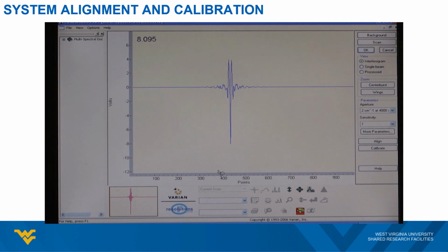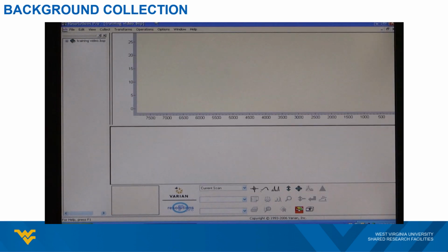With both alignment and calibration completed, click on the OK button on the right, and this will bring you back to the scan window. Now we are ready to perform the measurement. In contrast to other spectrometers, such as UV-Vis, an FTIR measurement typically involves 2 steps: capturing a background measurement and then capturing the sample's measurement.